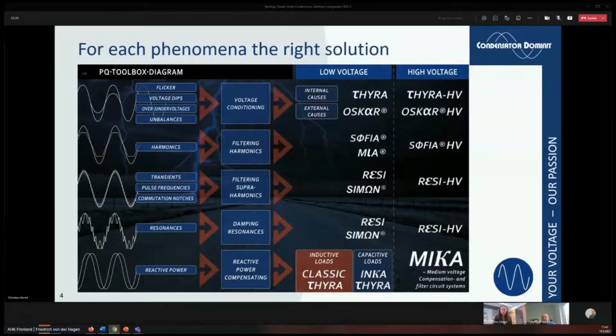The third issue in modern companies we see is a lot of high frequency disturbances. The Americans created the name supraharmonics. You can use that name, or you can leave it. Whatever it is, it's high frequency signals on your grid, which come from switchings of IGBTs or from commutation notches from DC drives or similar things, that can destroy switch-mode power supplies, rectifiers, and similar products. Not very nice to have in a factory.